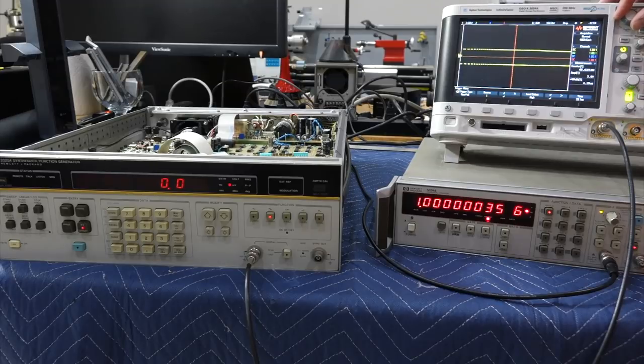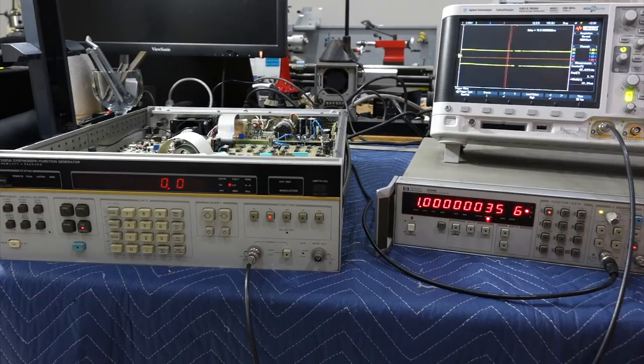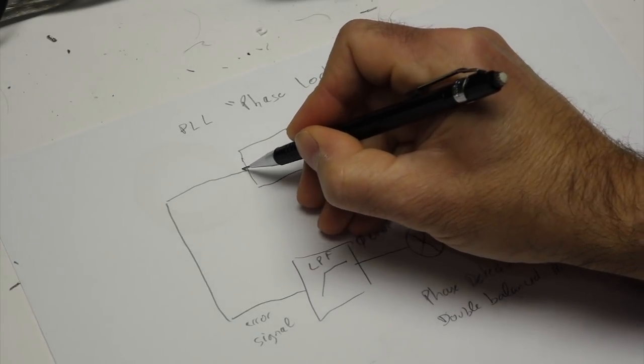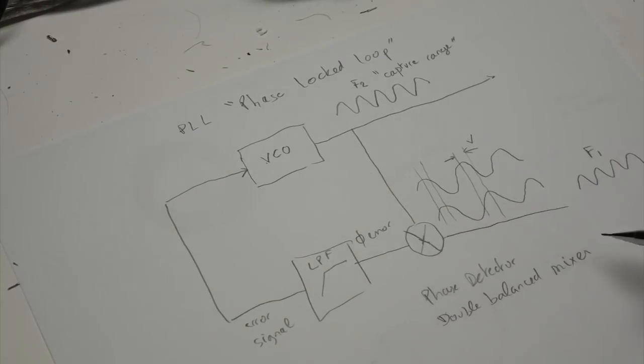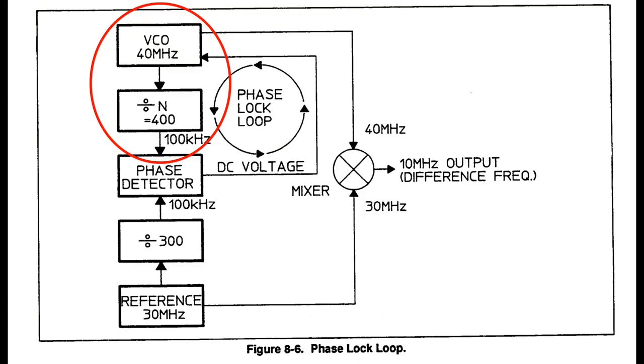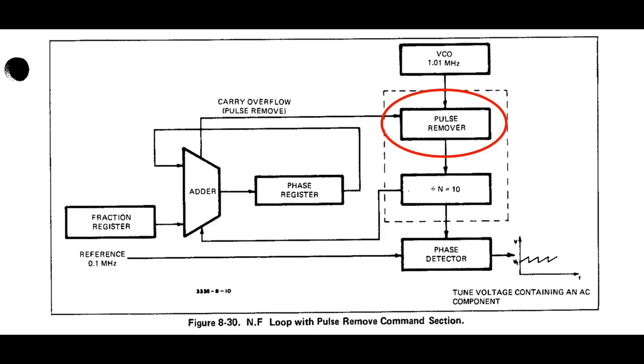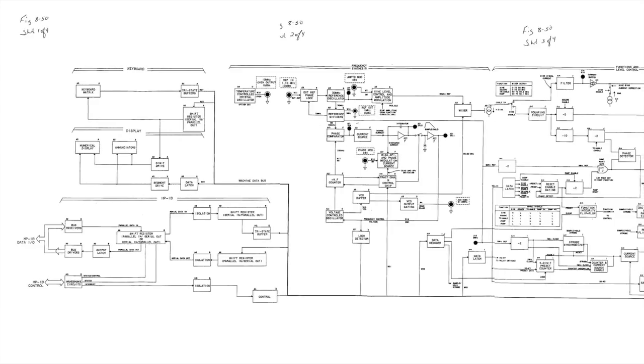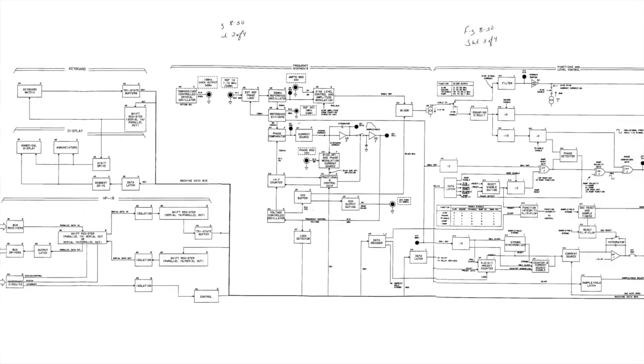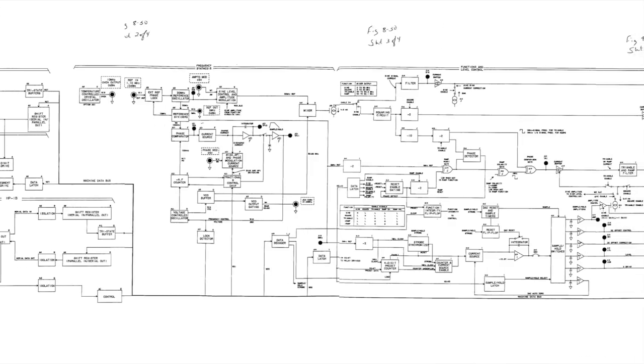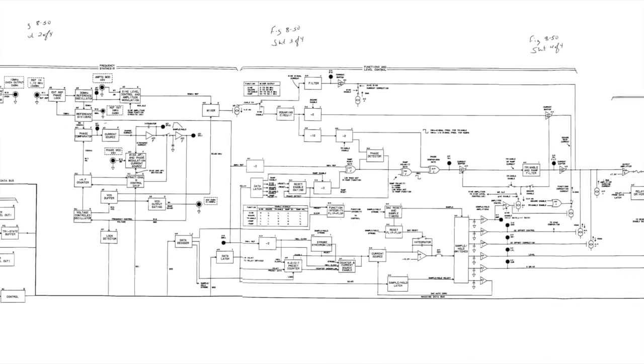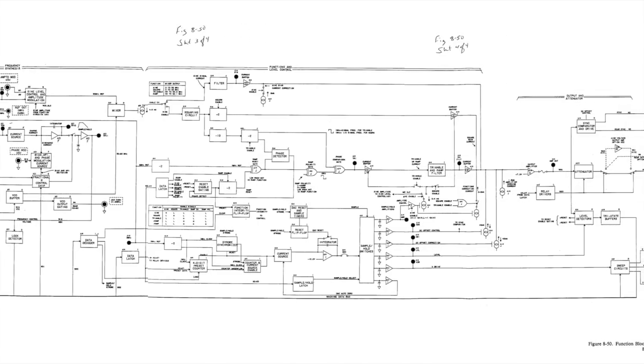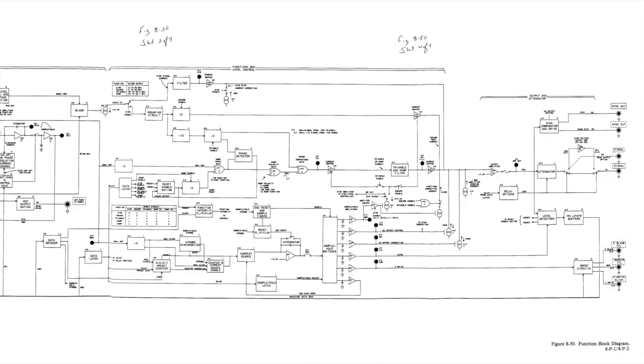I was actually hoping that my PLL loops were wonky, so we'd learn fractional-n synthesis, while debugging it. This instrument uses an incredibly clever frequency synthesis, where a classic PLL gets complexified with a divider and a multiplier to form the n loop, and then further complicated by a pulse remover to do fractional-n, and then polished by a digitally driven analog correction. But it turns out, the fault was elsewhere. I started the usual routine of adjusting the power supplies, and they looked all fine at first.